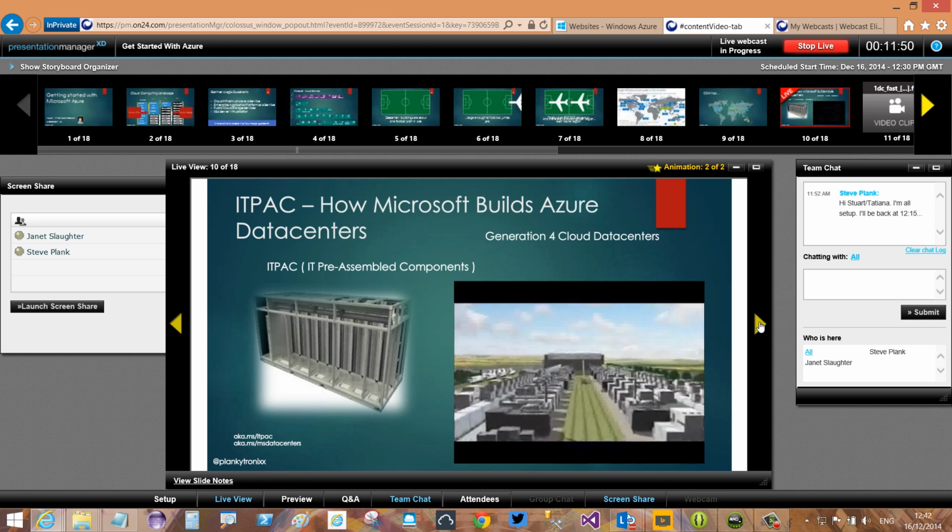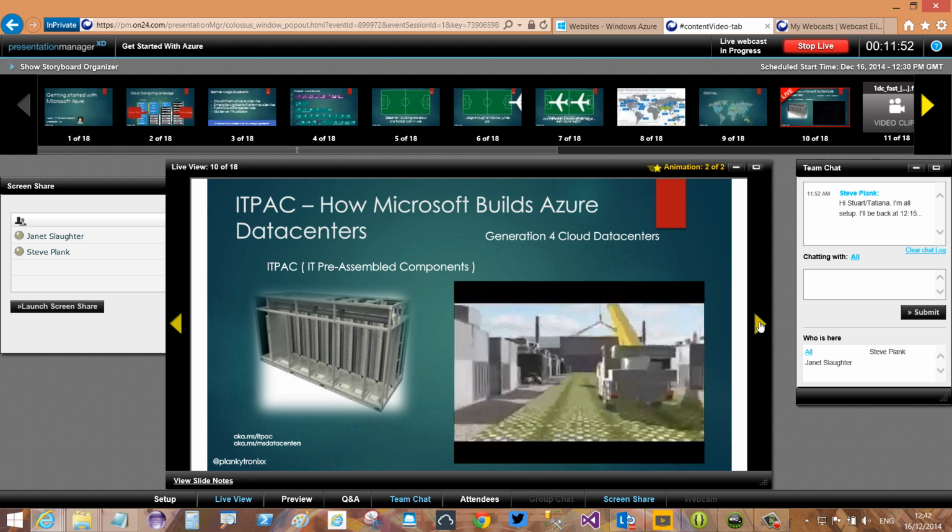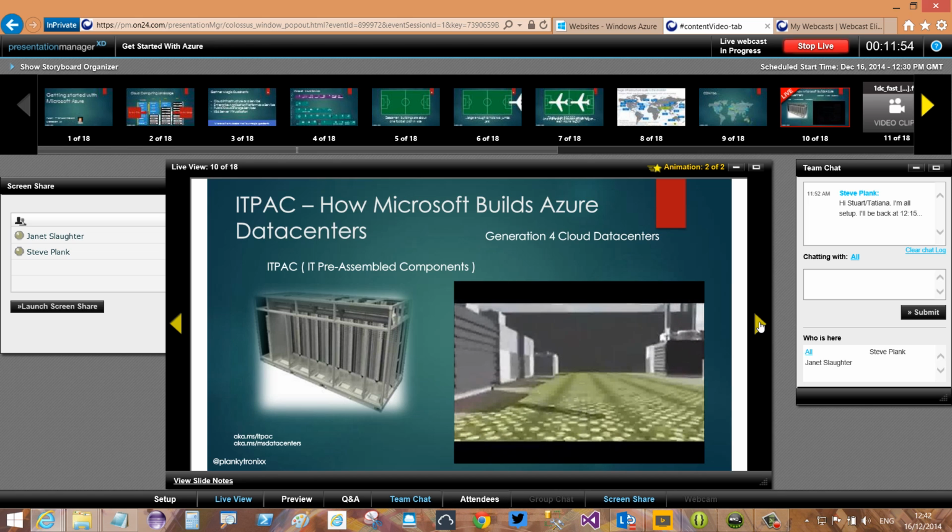Look at these data centers. Look, this is a Gen 4 data center. All the stuff is outside. It doesn't live inside a building. Each of these units is hermetically sealed, and the human being will never go inside them and never need to. The sort of thing that happens is the container is the replaceable unit. So we'll wait until we've got a couple of hundred failures in there, and then that'll be the trigger. It might be 300, it might be 100, but we'll hit some threshold, and that will be the trigger to cause a swap to occur.